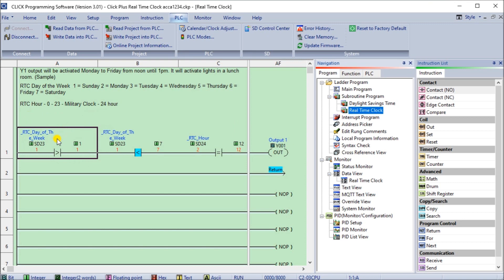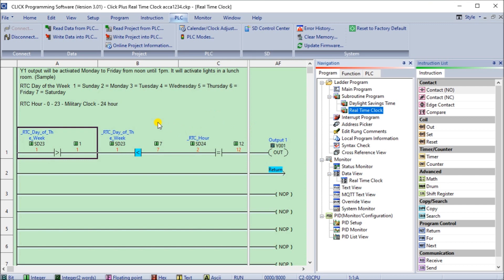So it basically demonstrates the bits here. So here we have the real time clock day of the week, so we have to be greater than one and we have to be less than seven, so we know that we are Monday to Friday. Then our hour, we're just looking for 12 o'clock, so it's going to be 12 o'clock to the full length of 12 o'clock, and then that'll be on and then our output here will turn on.